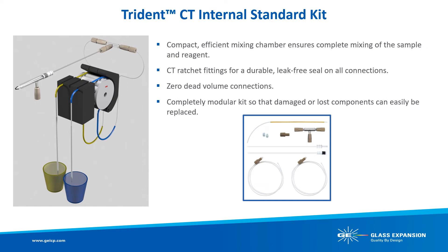Most ICP laboratories use an internal standard to compensate for interferences and enhance both short-term and long-term reproducibility. Glass Expansion's new Trident CT provides an easy and accurate solution for dosing all of your samples with internal standard without extra effort or the risk of error or contamination. The Trident CT is installed between the nebulizer and peristaltic pump. The kit is completely modular so that worn components can easily be replaced, and each kit includes a compact, efficient mixing chamber ensuring complete mixing of sample and reagent. Inert, metal-free CT ratchet fittings provide simple, leak-free connections every time.